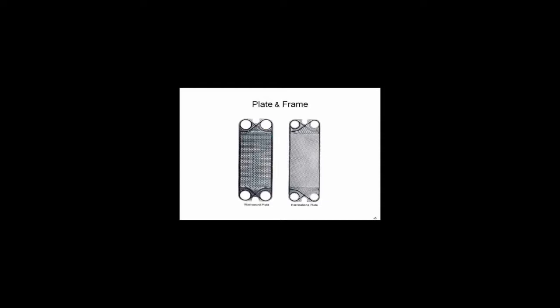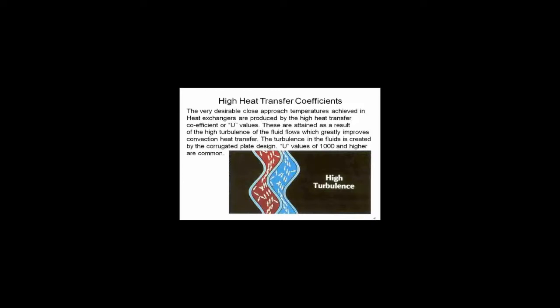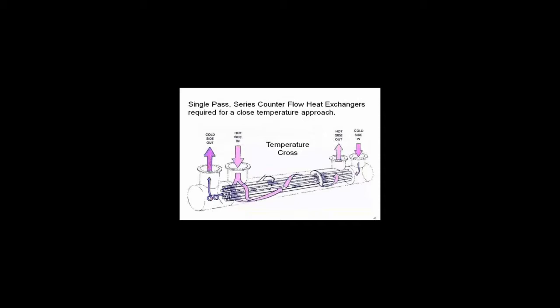But this is a typical plate, and the whole idea behind the plate heat exchanger is high turbulence. To get the U factors up, you can get some extremely high U factors on a plate heat exchanger when you create turbulence with these different types of plate designs. That's the whole concept. So what we're trying to do specifically with a plate or any heat exchanger, we want to maximize that U factor because it reduces the area down, reduces the first cost down, and makes it affordable. And that's the thing we're looking for, is the highest U factor we can possibly get so we can come up with the most economical selection of a heat exchanger. Typical U factor on a plate can be as high as a thousand, and it's not uncommon to see those kind of numbers.